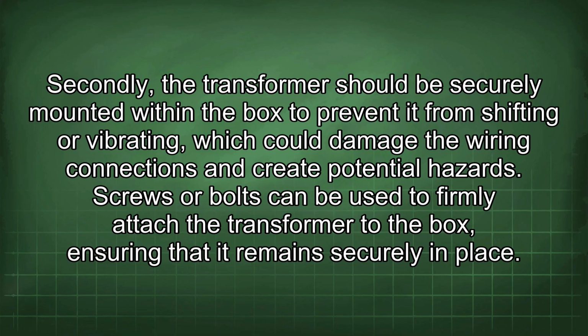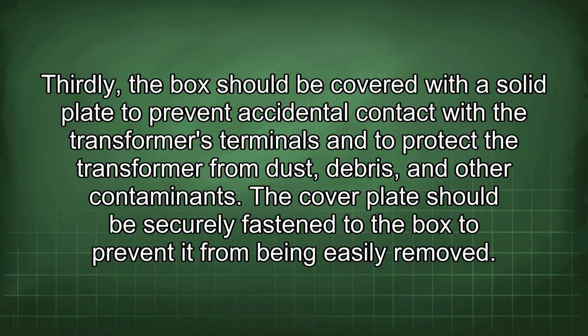Secondly, the transformer should be securely mounted within the box to prevent it from shifting or vibrating, which could damage the wiring connections and create potential hazards. Screws or bolts can be used to firmly attach the transformer to the box, ensuring that it remains securely in place. Thirdly, the box should be covered with a solid plate to prevent accidental contact with the transformer's terminals and to protect the transformer from dust, debris, and other contaminants.